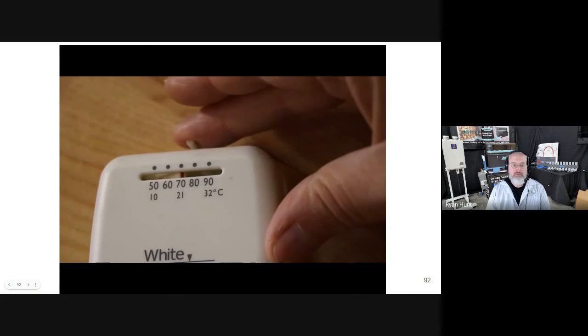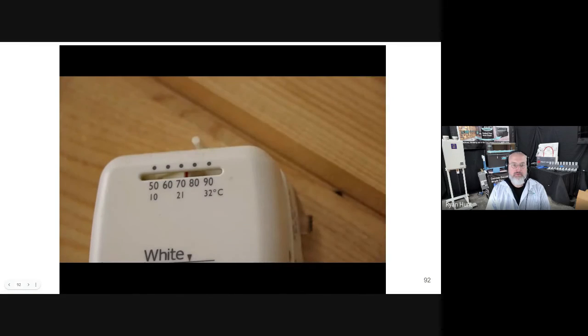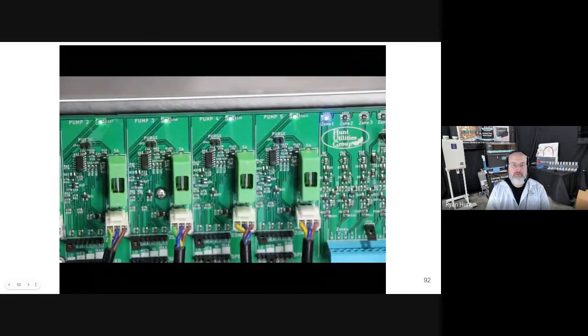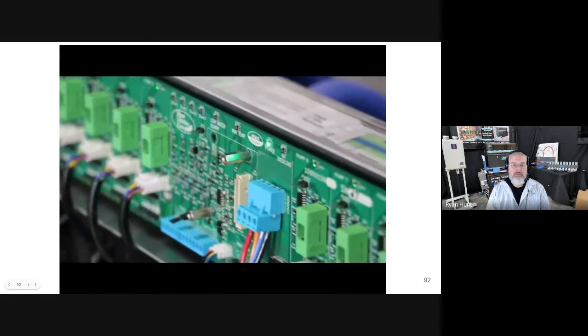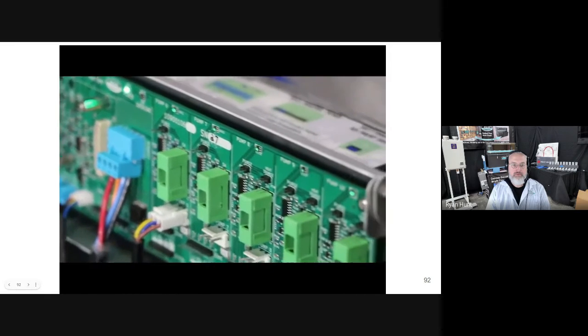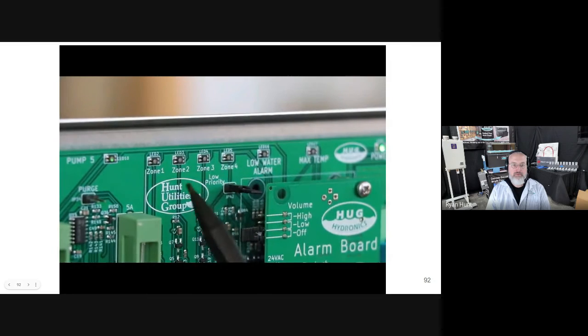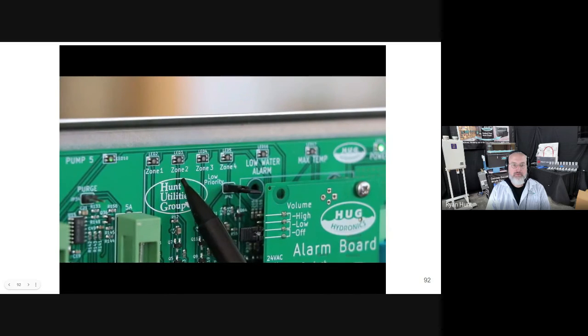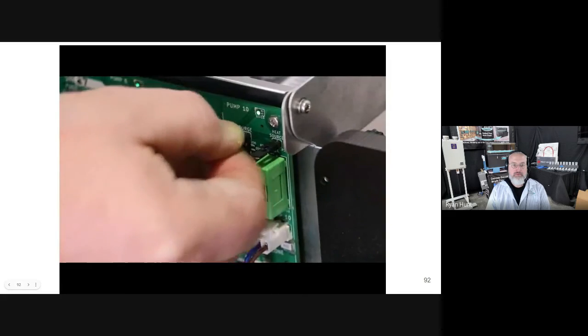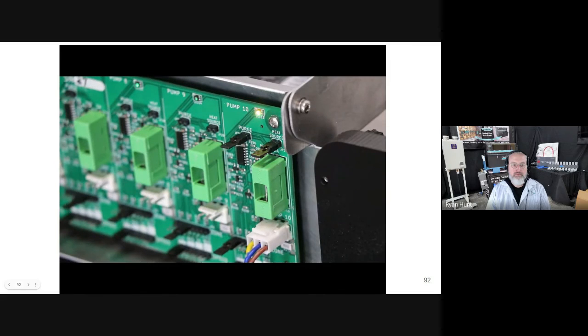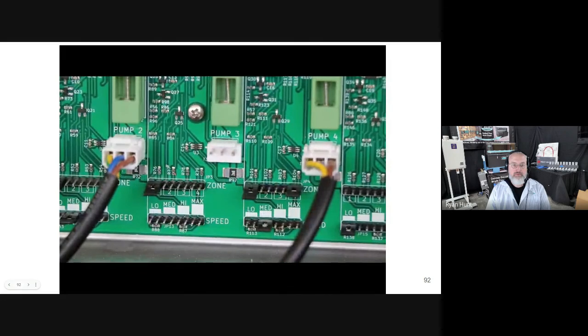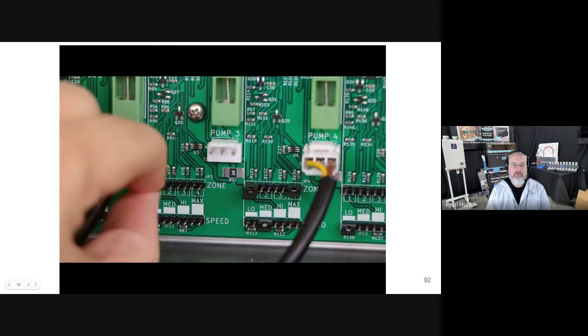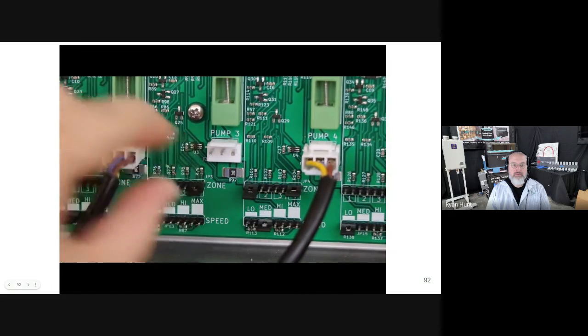Each active thermostat should show a blue zone light at the top of the board, above the thermostat connector. All pumps should be active, each indicated by a green light getting brighter. Now, let's assign the thermostat zones for each pump by moving the jumper to the correct zone. Each pump has its own section of the control board, labeled 1 through 10. Pump 10 is always to the heat source.